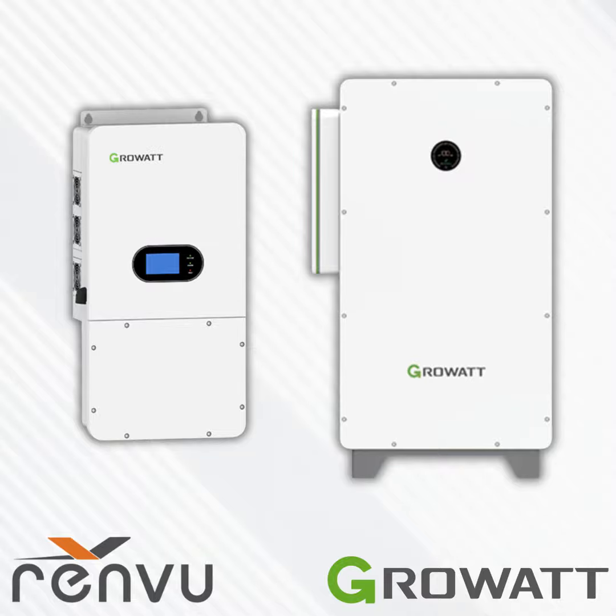So this is what I mentioned of when you use multiple SPH inverters in parallel, of how you can connect them together to build a 120/208 volt three-phase system. This is what the diagram would look like if you have two inverters in parallel and you're still able to cover all three lines. And this is what it would look like for three inverters in parallel. And you can do up to six. So if you have any questions on how you would use this inverter in parallel or what the diagrams or configurations would look like, feel free to contact either RENVU or Growatt, and we're happy to assist in answering those questions.